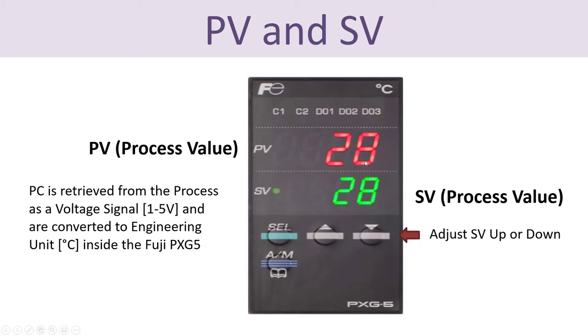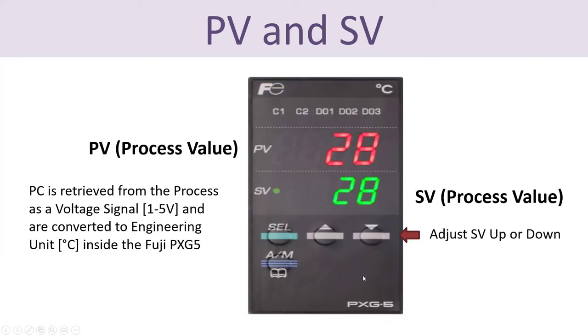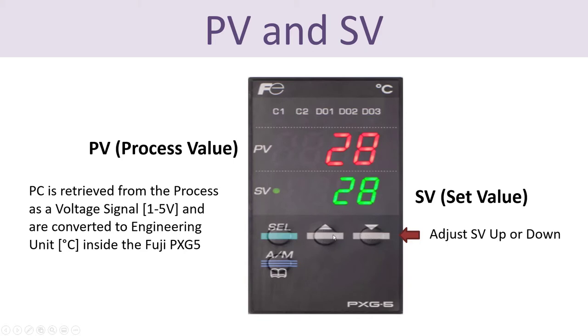When we have done the correct wiring on the back side, we mainly use the front panel to set the set value and read the process value. On top we have the PV or process value, and in the bottom we set the SV or set value. In green we have the set value and in red we have the process value. The process value comes from the process while we set the set value here, and based on that the PID controller calculates a proper control signal and sends it back to the process. We adjust the set point by clicking the up and down buttons.